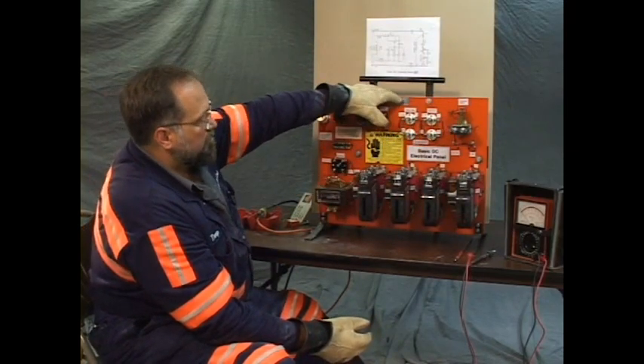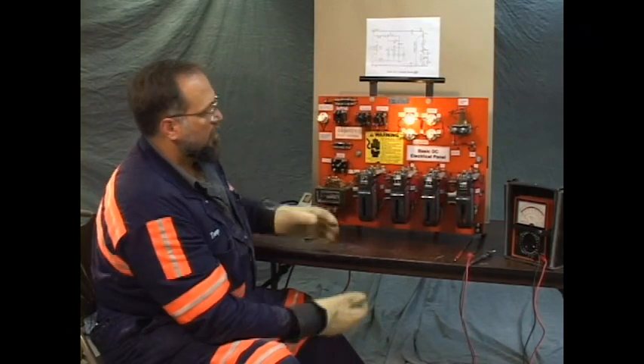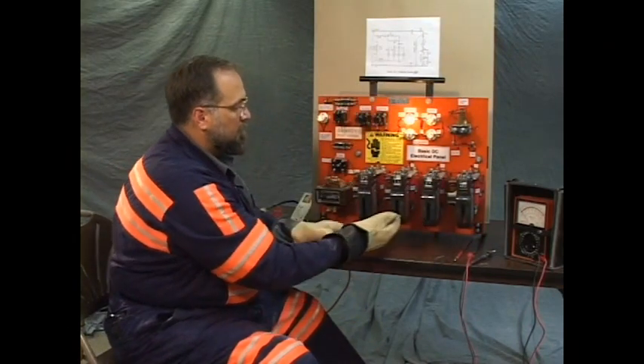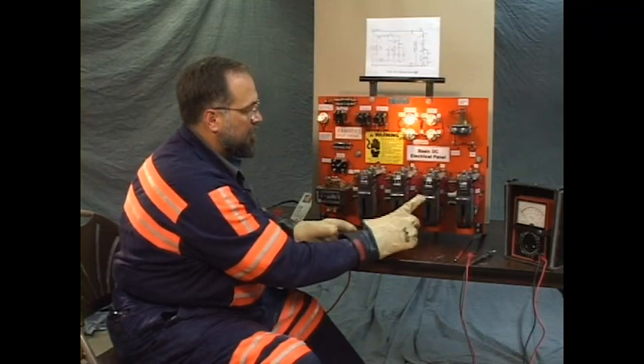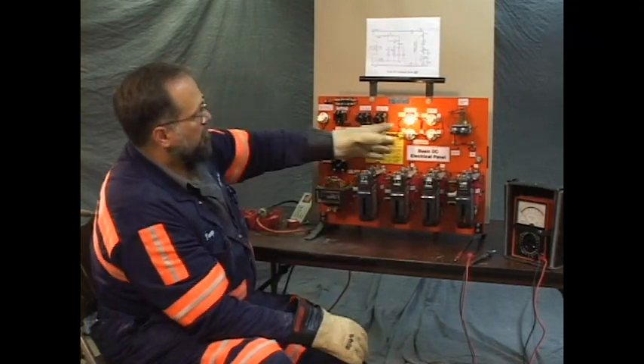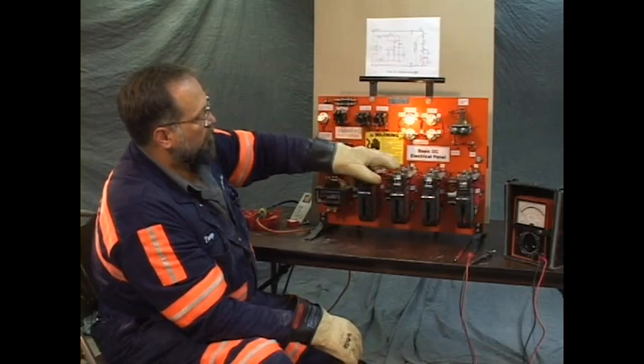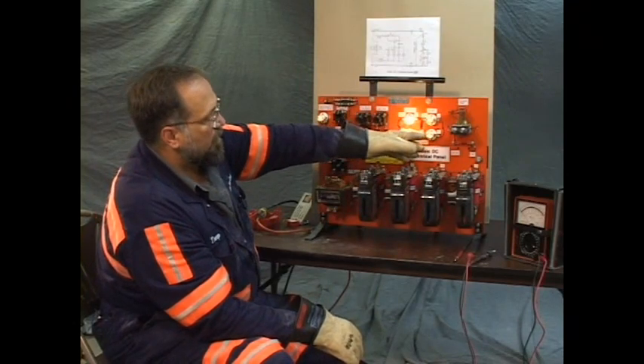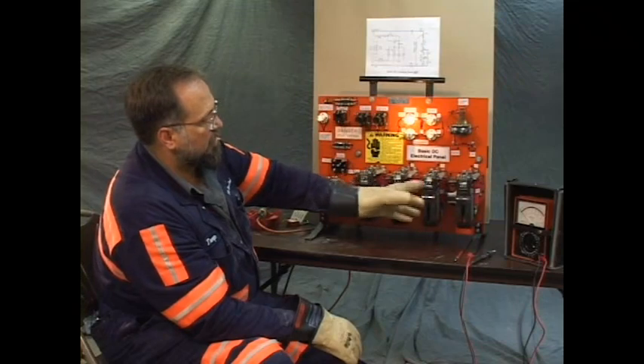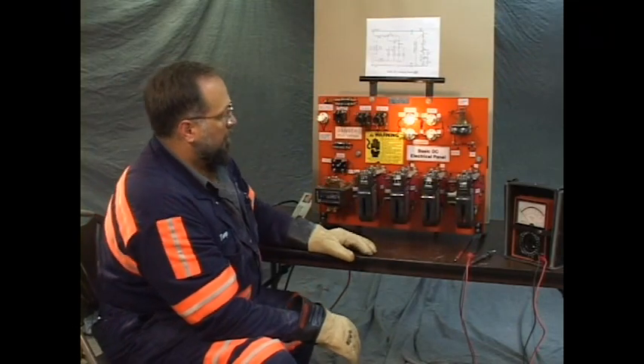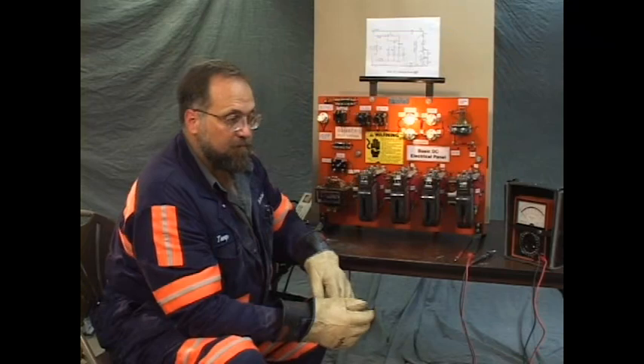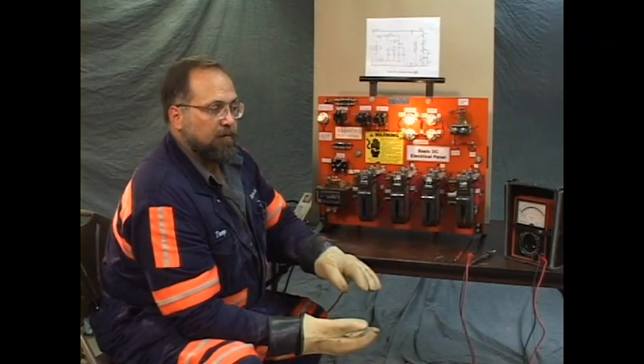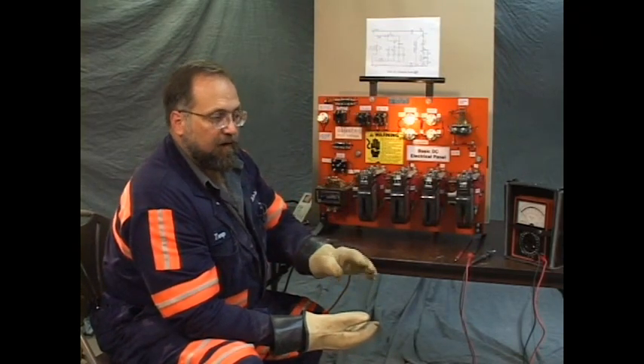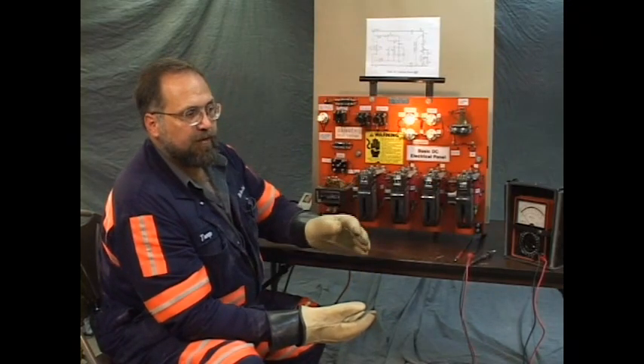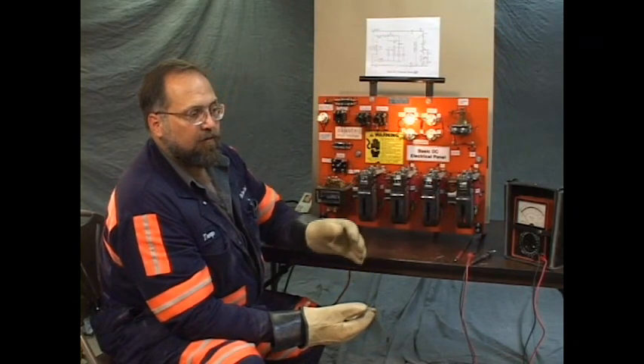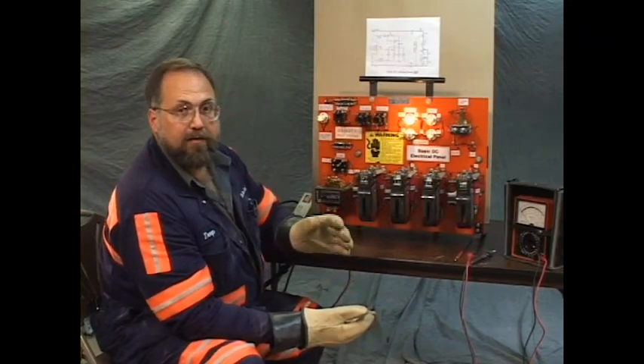Let's try it again. M2 and M1 closed, 1A closed, 2A never did close, stayed down. This light went off when 1A closed. 2A still on. This contactor didn't go in. So there you have it. If this was a motor on a piece of mining equipment, you would start and you'd have low tram, and then you'd have an intermediate speed, and it would never cross over into the highest speed. It would stay at a medium speed.